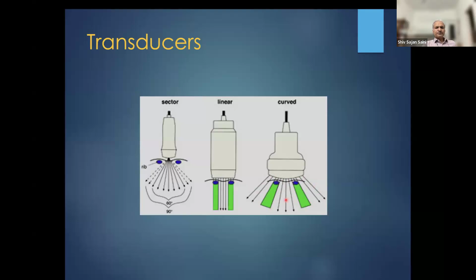And this is usually used for very high frequency measurement, say something like 10 to 15 megahertz. The other is a combination of these two. This is a curvilinear probe, where the footprint is much larger, and accordingly the user interface shows you a curved combination of sector and a curved visual depiction of the ultrasound tissues on the user interface.